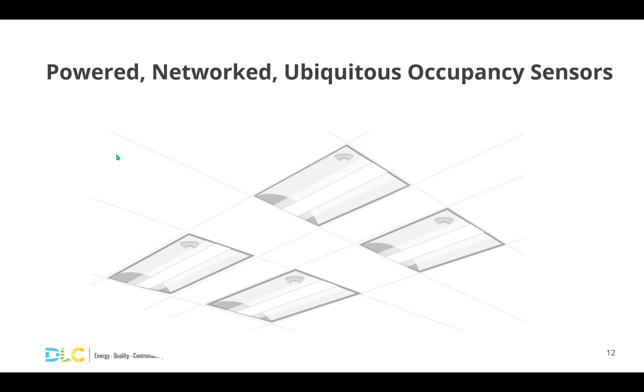Still, when network lighting controls do make it past value engineering and get installed, they provide powered, networked occupancy sensors throughout a space. In suitable buildings, signals from those sensors can inform HVAC controls to relax temperature set points by a few degrees in unoccupied areas.